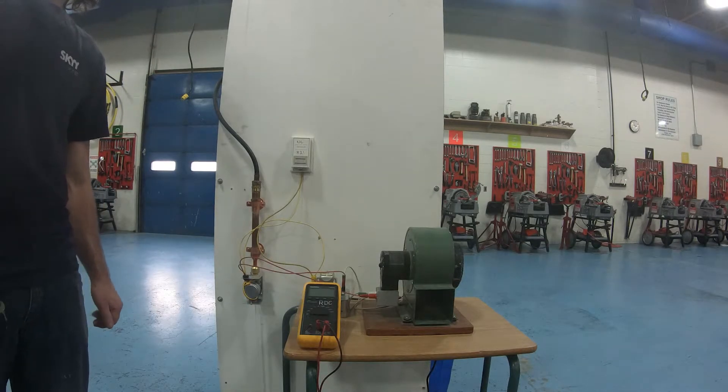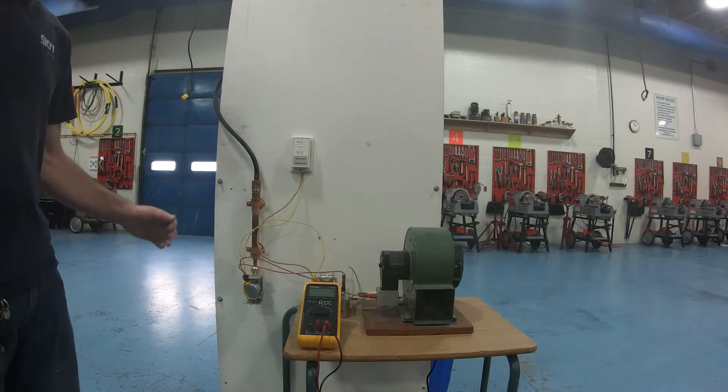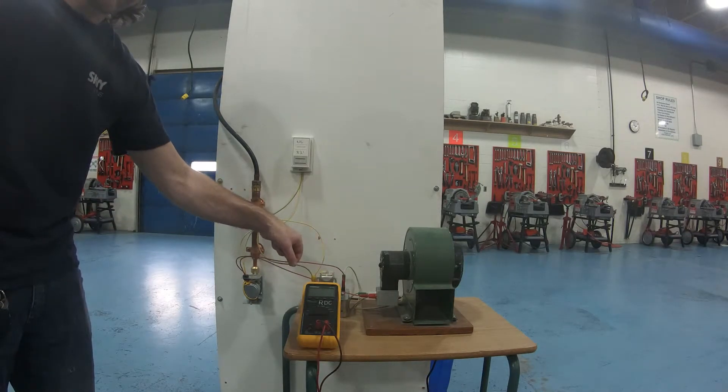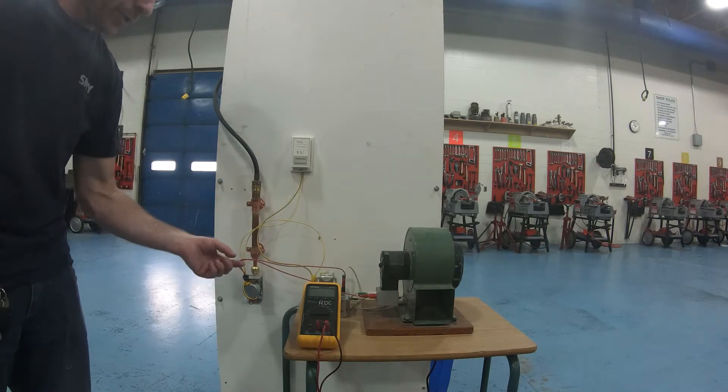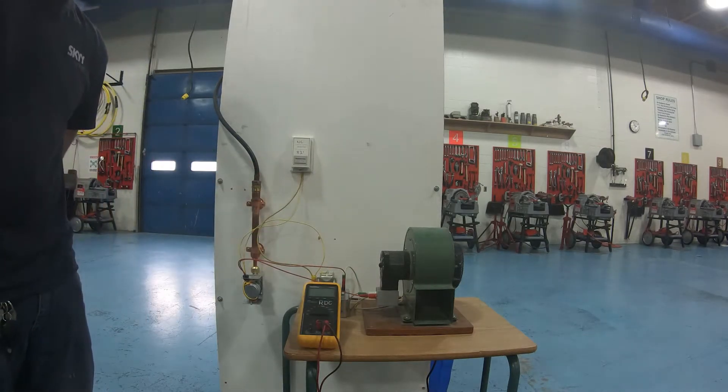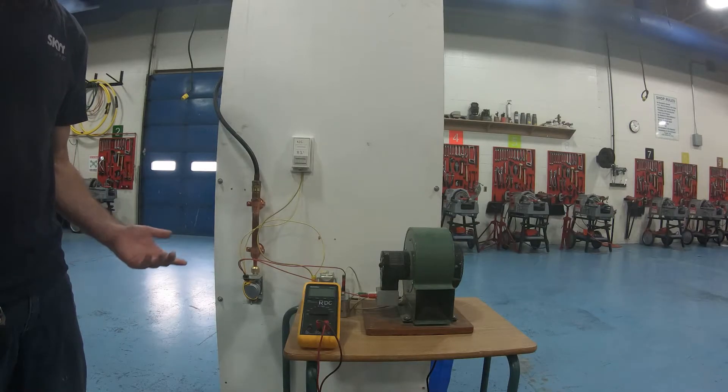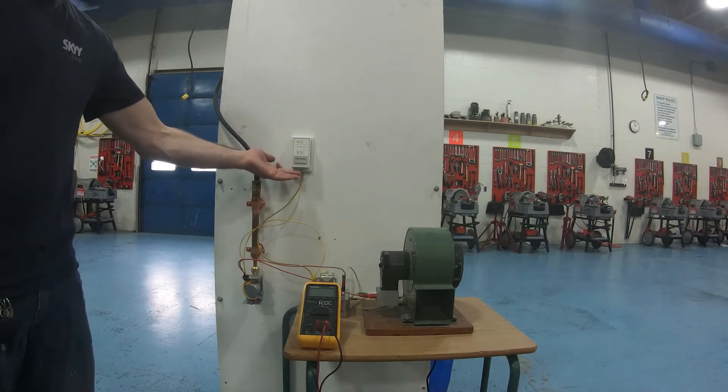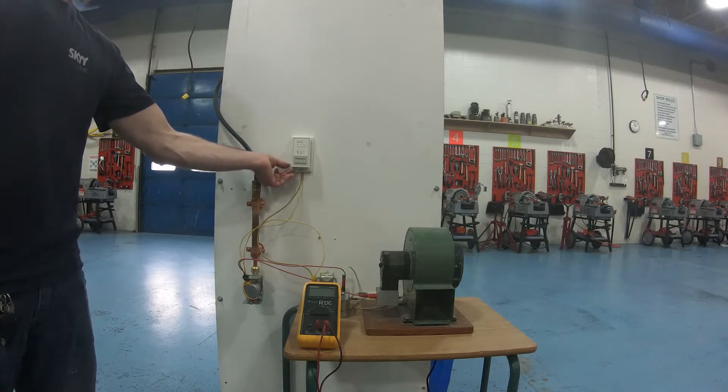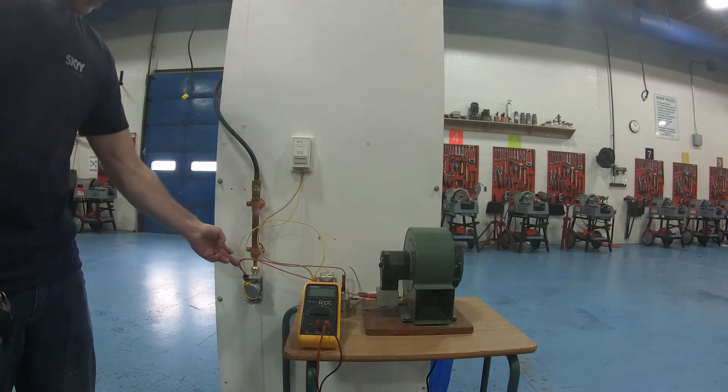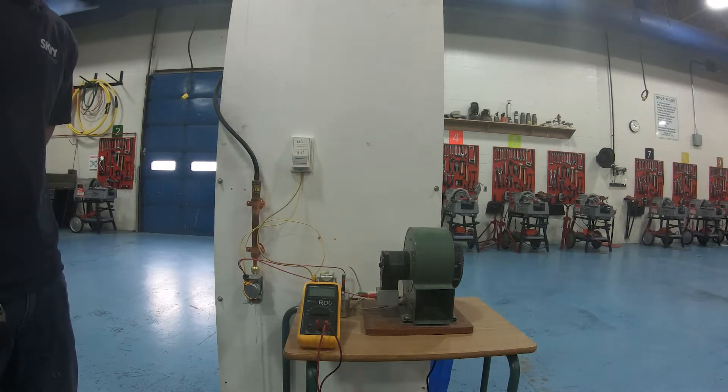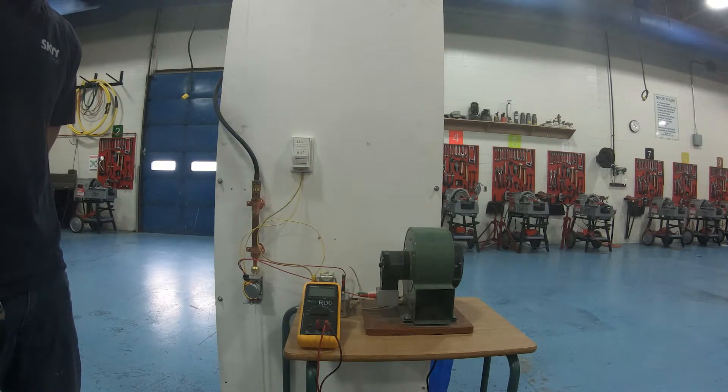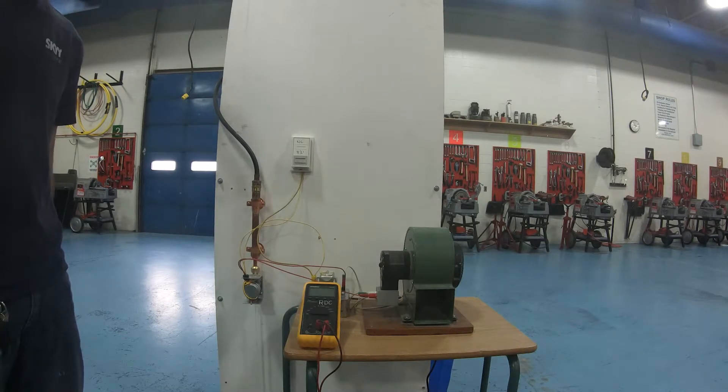And I'm just going to let it go and it'll seal up again. So what I have here, I have 120 volts, well 116, coming through this red wire to my end switch and the other side of that switch comes out to this fan here. Typically this would be a pump, but pumps can't be run dry so we're not going to do that. So what I'm going to do is turn up my normally closed thermostat right to 30, and this will start to open up. When it gets all the way open, this fan should come on. Perfect. There. I just turned it off and it closes.